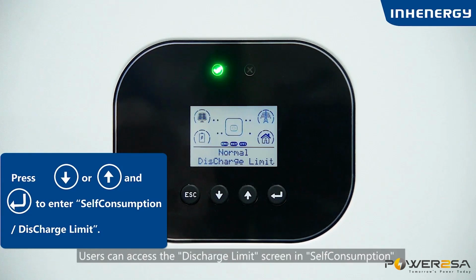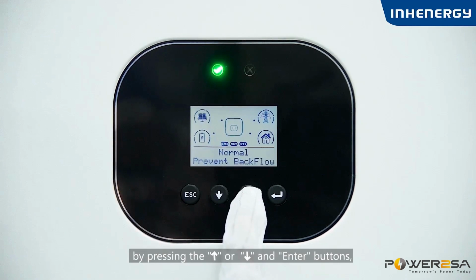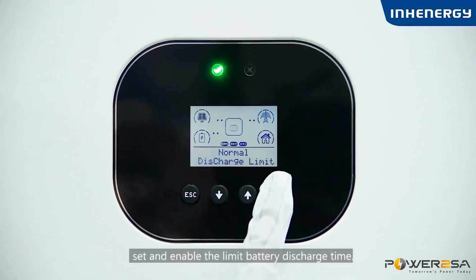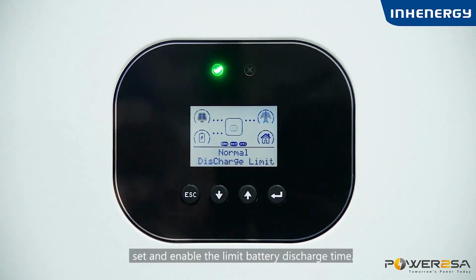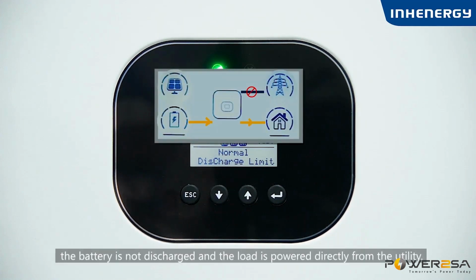Users can access the discharge limit screen in self-consumption by pressing the up or down and enter buttons. Set and enable the limit battery discharge time. During this set time period, the battery is not discharged and the load is powered directly from the utility.